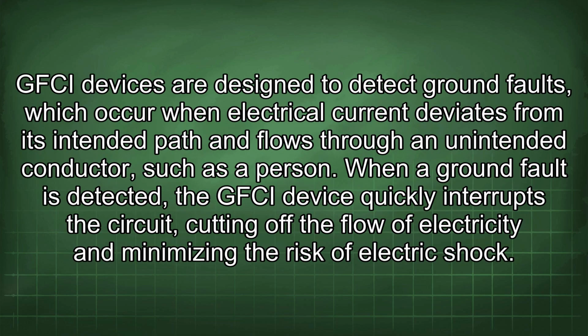GFCI devices are designed to detect ground faults, which occur when electrical current deviates from its intended path and flows through an unintended conductor, such as a person. When a ground fault is detected, the GFCI device quickly interrupts the circuit, cutting off the flow of electricity and minimizing the risk of electric shock.